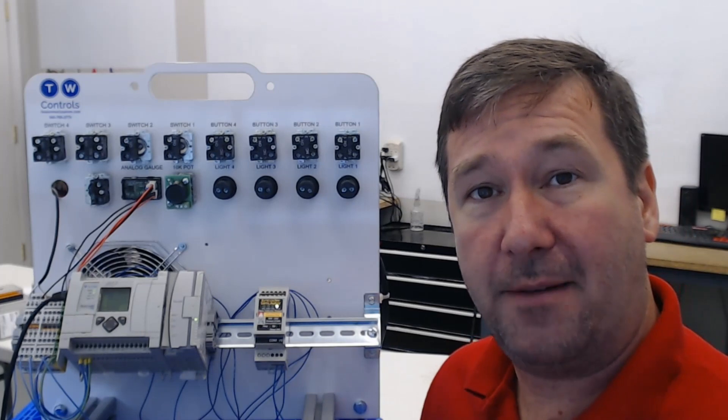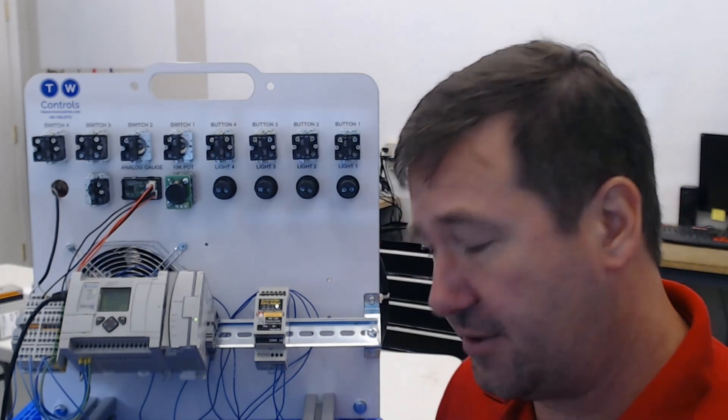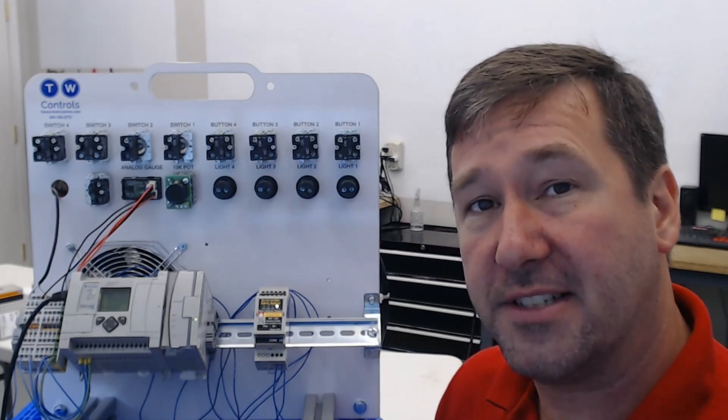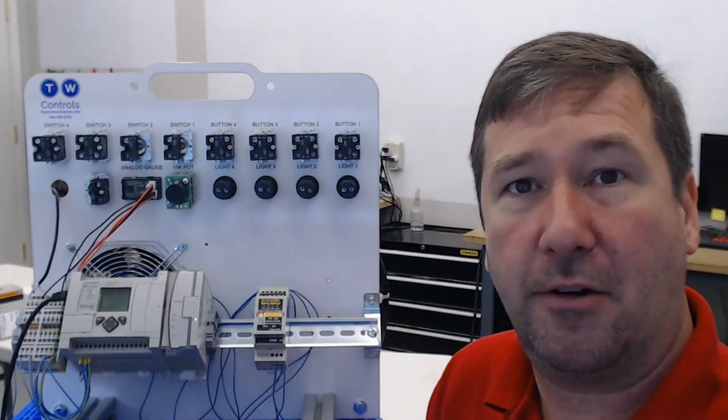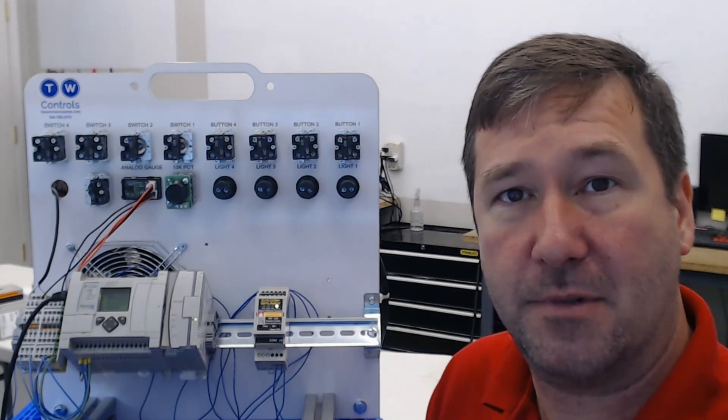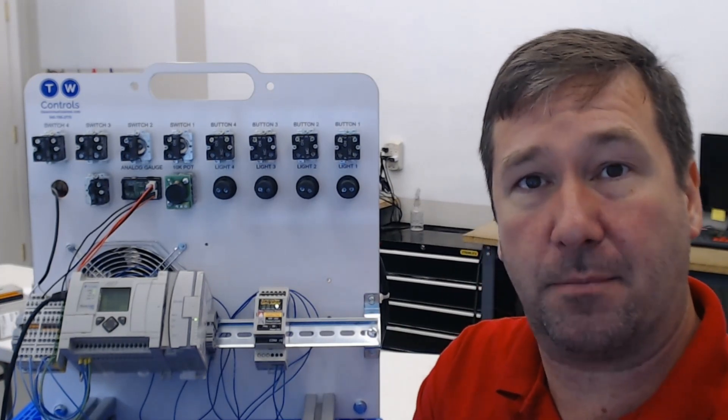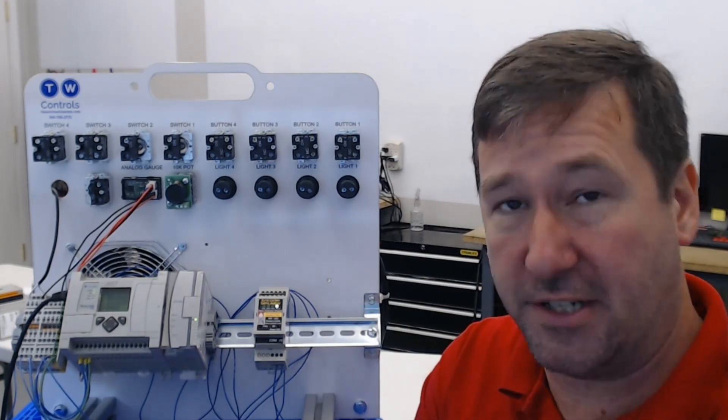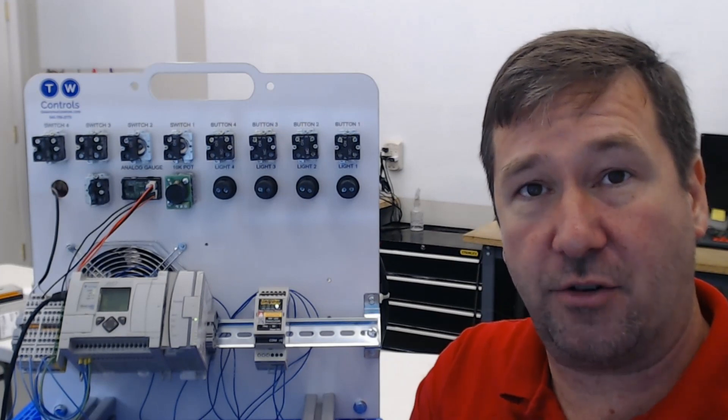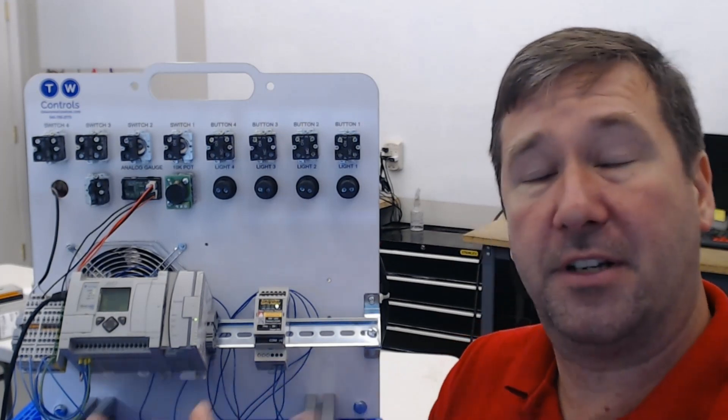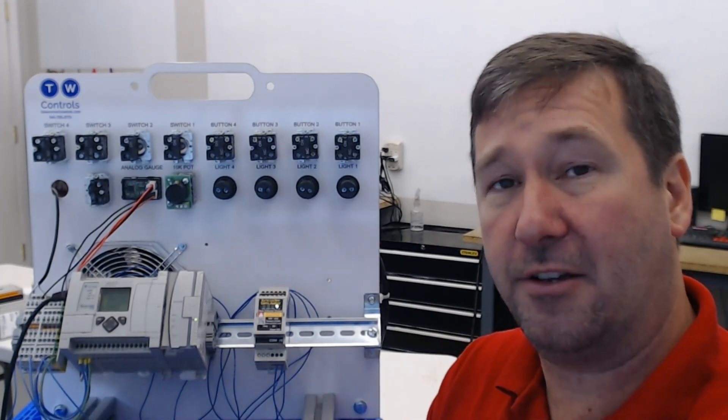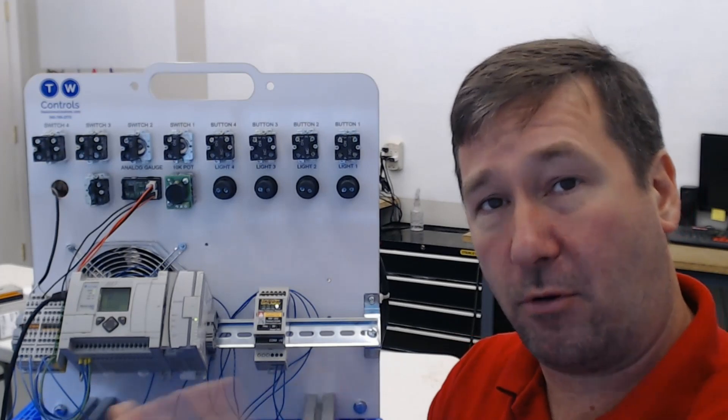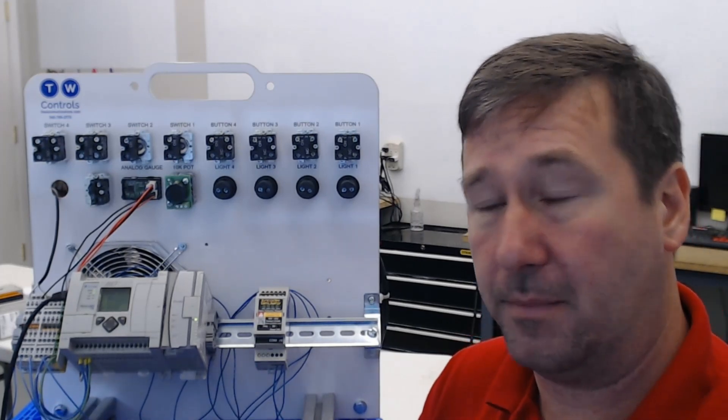So is there ever a time that you need to hit the no button? Well yeah, there's two reasons to hit the no button. Say you're building hundreds of the same machine, and you have a default set of parameters that you don't want to change normally, then you would hit the no button there. That way, you're always downloading those default parameters to the machines as you're building them.